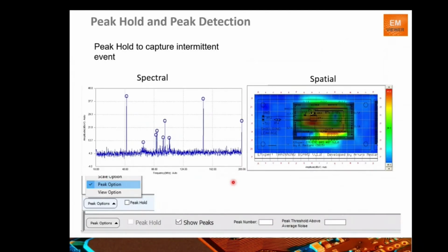Peak hold and peak detection, that's another thing that's very important. Sometimes you have intermittent interference. It's coming and going. There's no way to synchronize to that, and it's very difficult to capture. So the way we are addressing that is we're turning on a peak hold and a continuous run. We simply continue to make scans and hold the highest value until eventually we capture the interference that is very difficult to synchronize to.